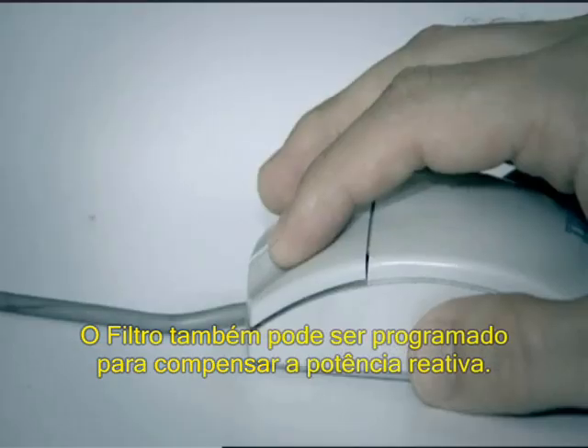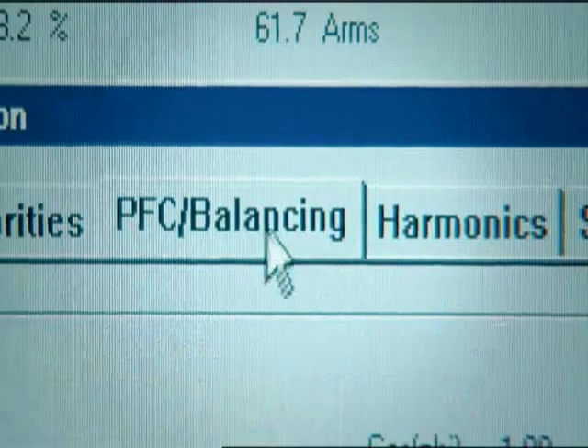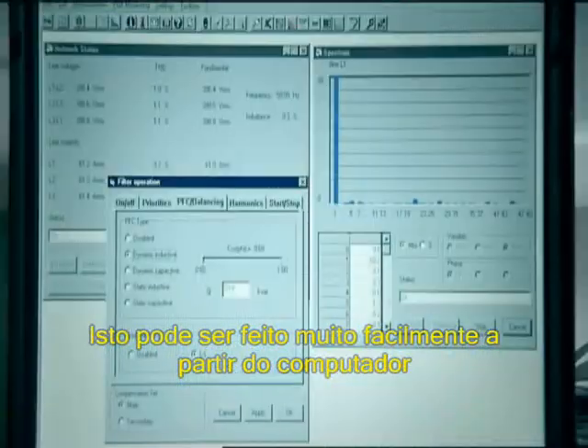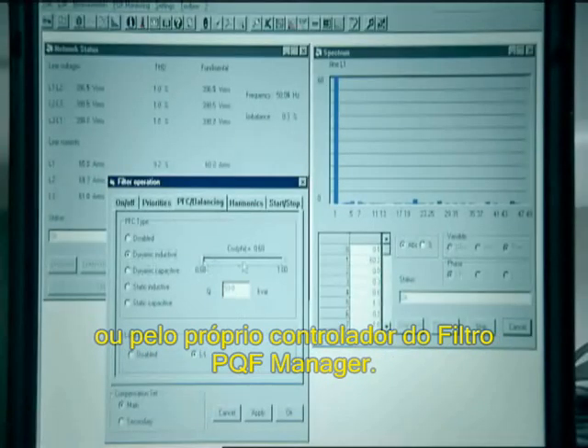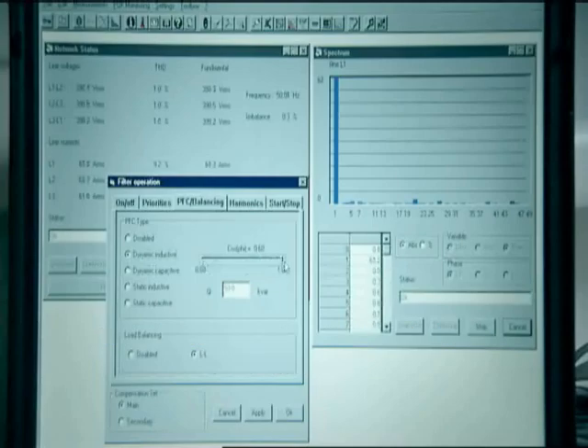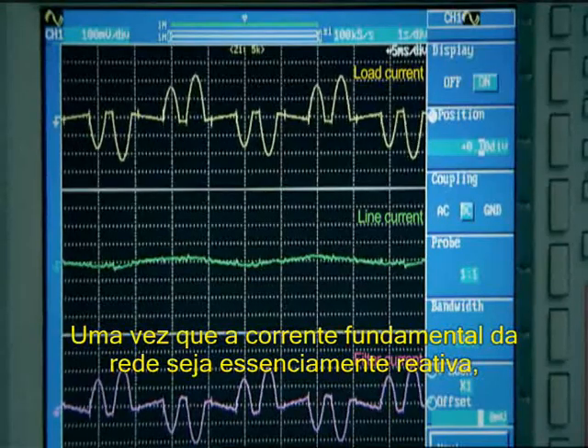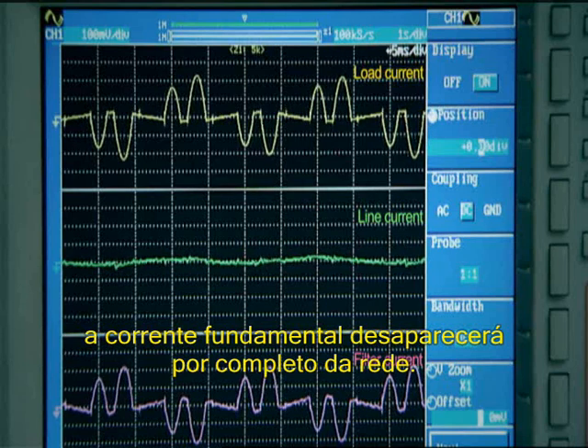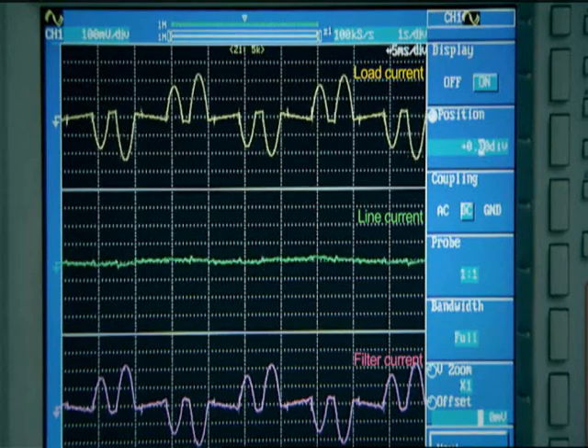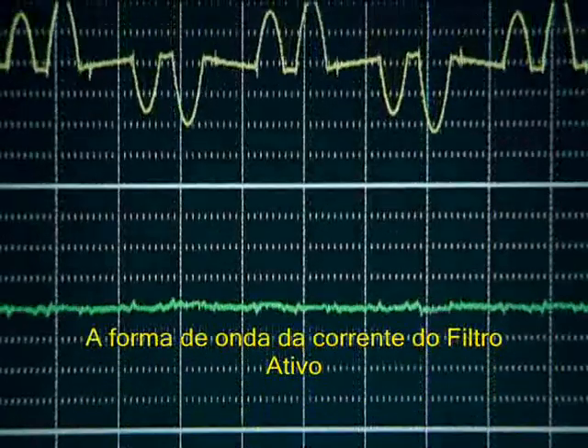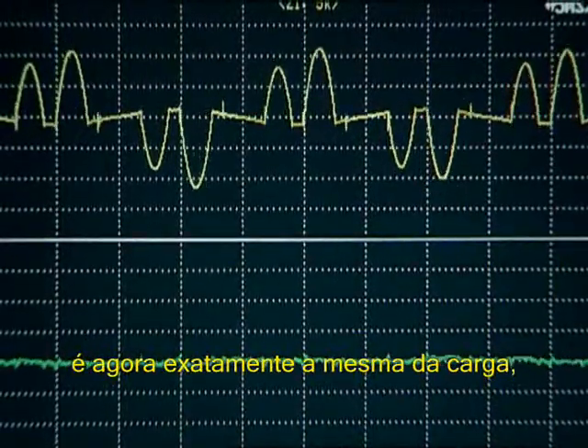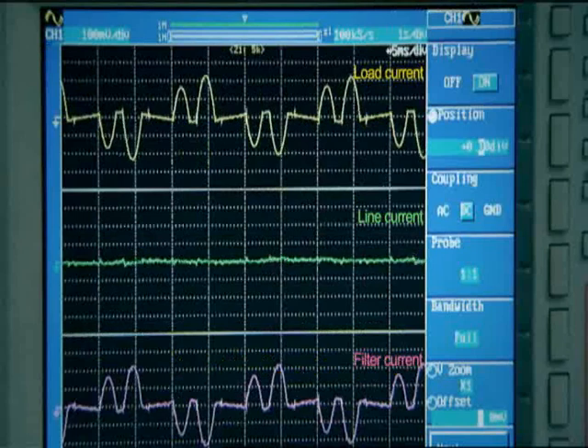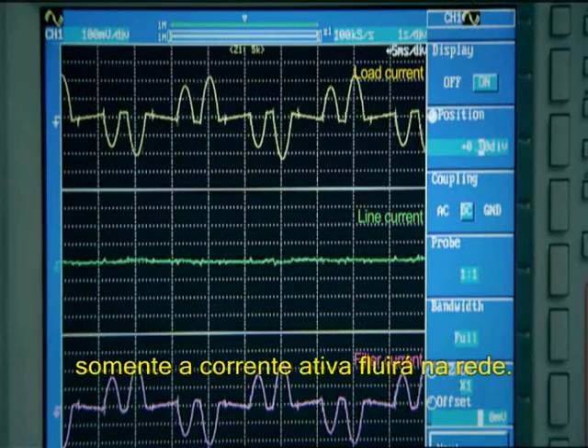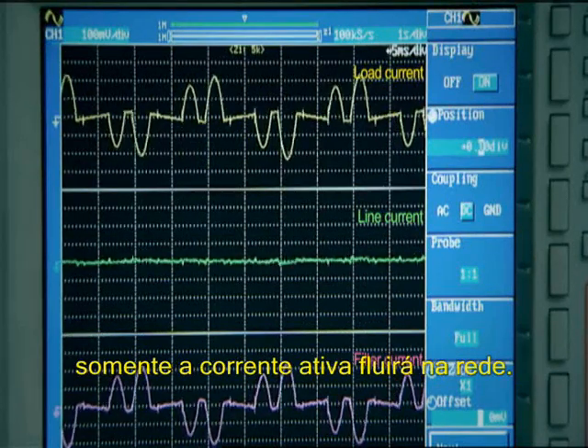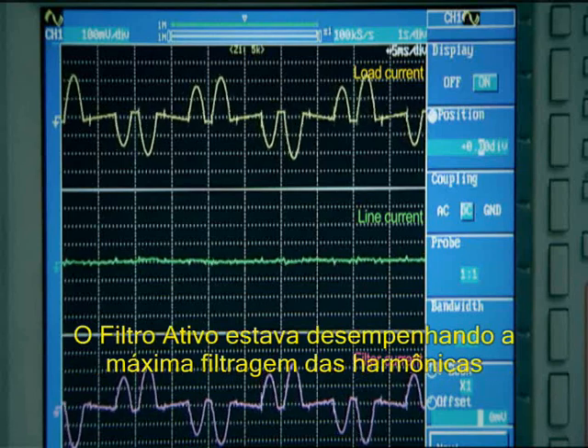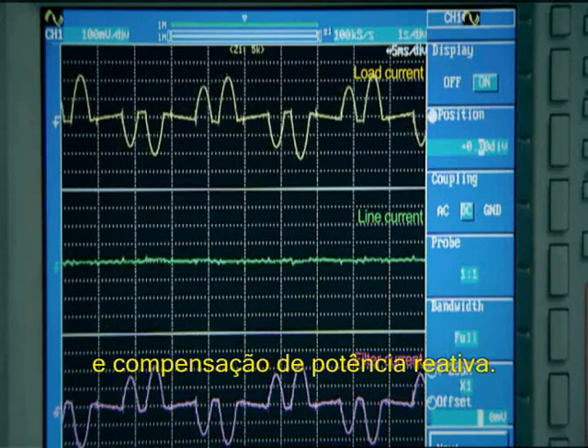The filter can also be programmed to compensate reactive power. This can very easily be done from the computer or the PQF Manager filter user interface. Since the fundamental line current is mainly reactive, the fundamental current will disappear from the line. The current waveform of the active filter is now exactly the same as the load, but in phase opposition. In a real industrial application, only the active current would be flowing in the line. The active filter was performing maximum filtering and reactive power compensation.